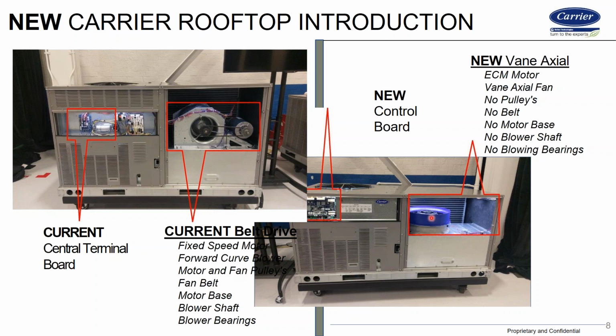Okay, so airflow is the big one on these, and then don't forget to set the dip switches, your ABC and your rotary switch. If you leave it at factory settings, which is B, and roughly around 70% on the rotary, you may not have enough airflow with that particular duct design, especially if you're internally insulated duct. Think about all the factors that cause high friction rates, in turn causing high statics. So all those things together equate into limit tripping and problems, okay?